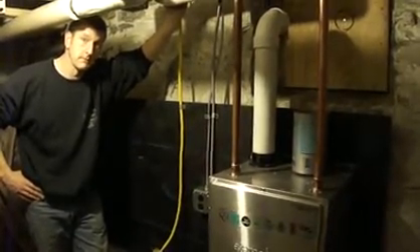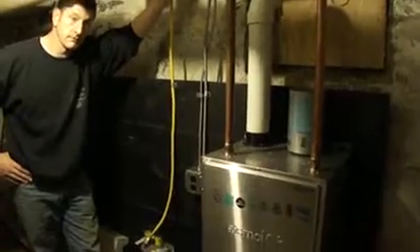Now, just tell me a little bit about this 80-gallon reserve tank. How was that selected in the process? Does it come with the Eternal, or is that something that in this application was just important for the usage? Basically, that tank creates a buffer for when, in this application, they have, I believe, 12 apartments that might all of a sudden all need hot water at one point. And it gives a buffer for any time when the demand can exceed what the Eternal might generate at one time. But for, let's say, a house of 6 people, this unit can take care of itself?